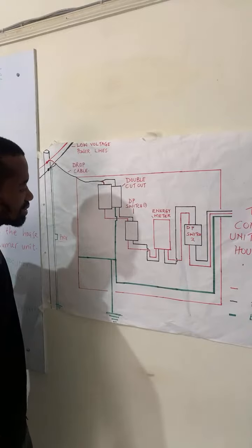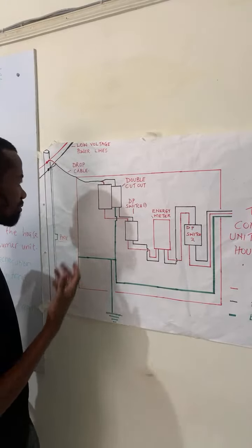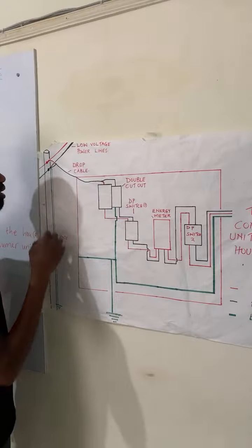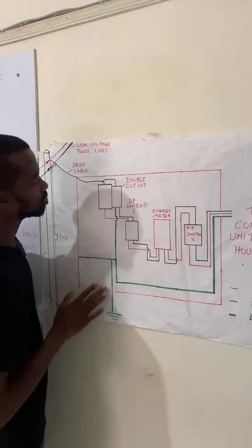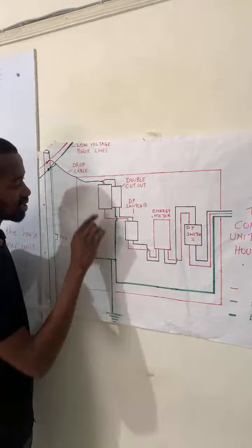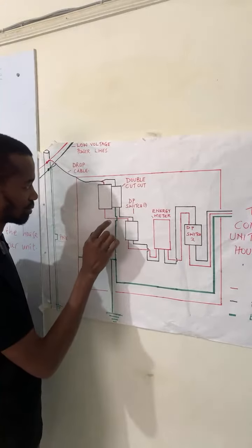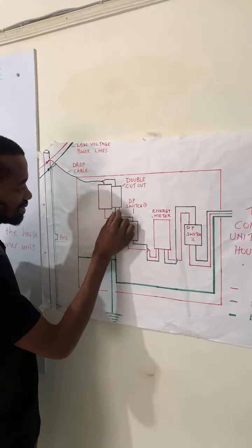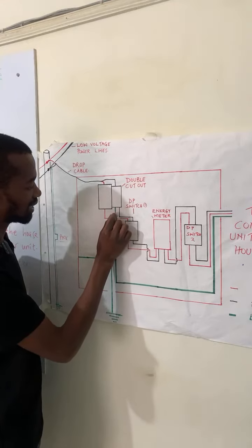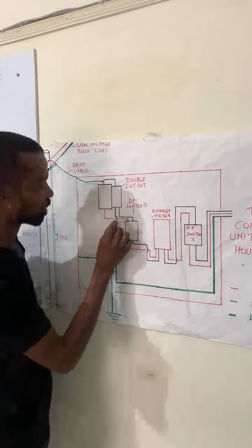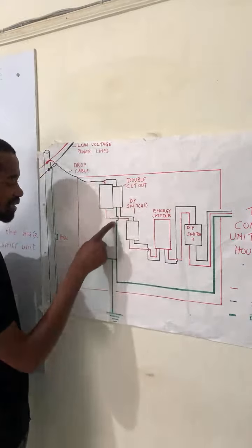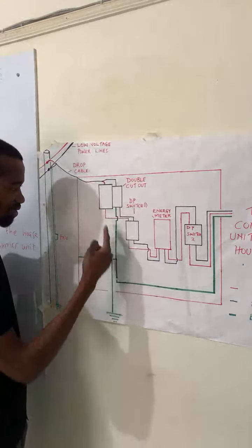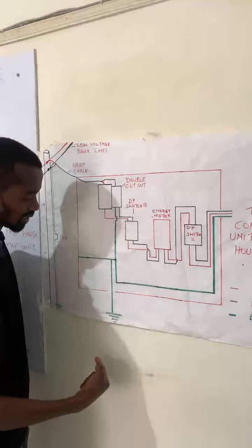We have been saying that the neutral is the return path for the electrical connection. Now, the phase will flow all the way to our cutout. At the cutout, we will tap the neutral at this output, and we will do what is referred to as bonding. This green line here represents the earth, and it will drop all the way to the ground through what we refer to as an earth rod. So the earth rod will come in handy at the meter box.